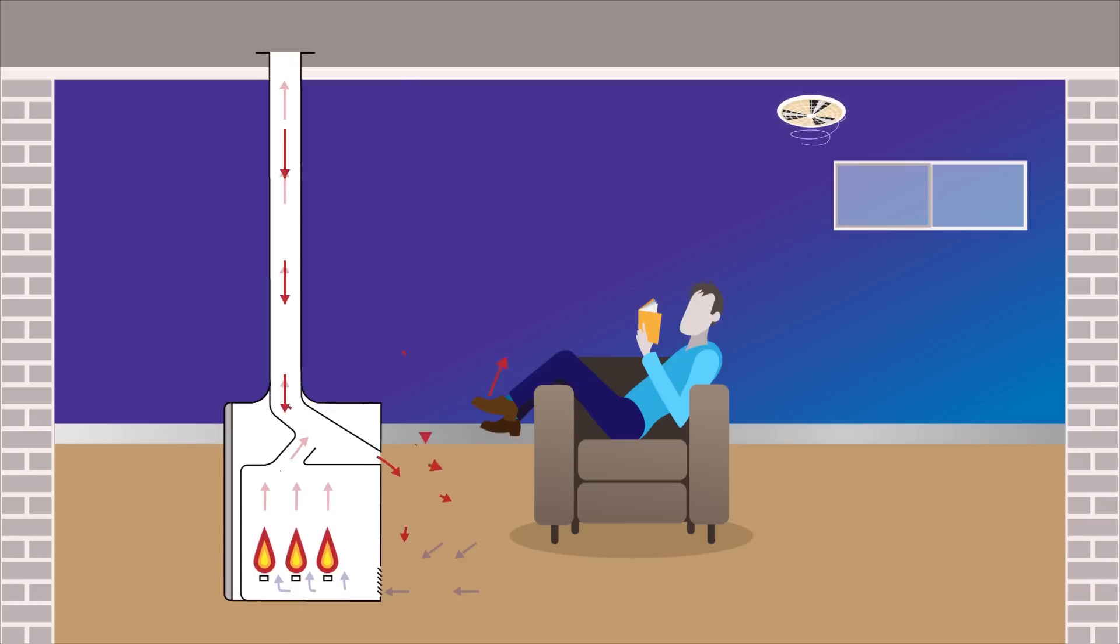In an open flue heater, the flue can operate as an opening to relieve the negative pressure. To prevent this from happening, install ventilation in the room to equalise the air pressure. This will enable the appliance to operate safely.